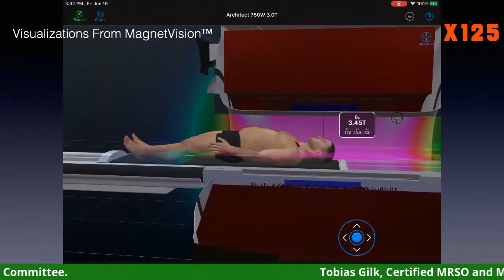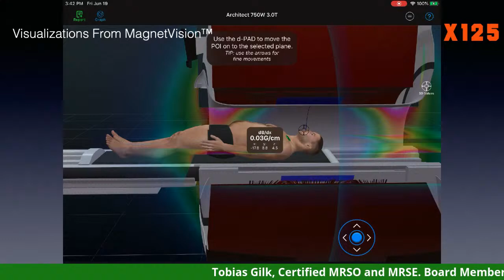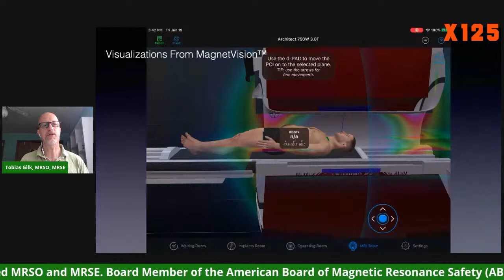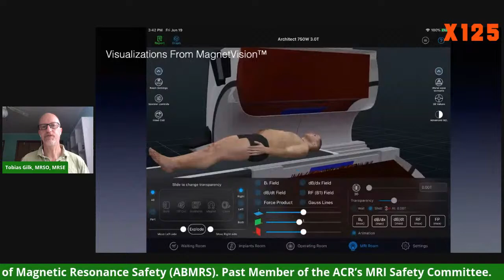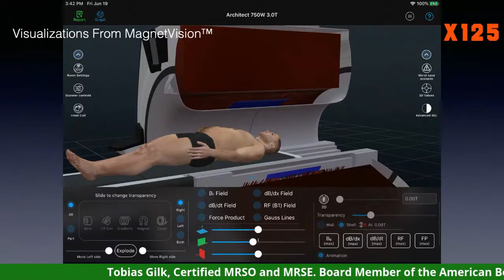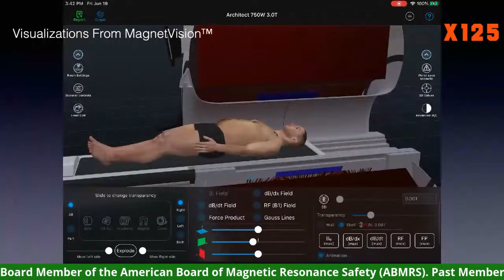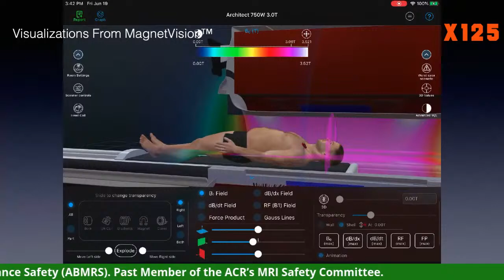And here we switch to spatial gradient. You'll see there's zero spatial gradient, or zero colorization, in the center. When we do point values, you can see that essentially it's functionally zero in the middle of the magnet. But you can see that there are regions near the mouth of the bore where the spatial gradient values are quite significant. It's incredibly important to have a good understanding. Let me see if I can just restart that animation. Here we go. Now you know what I'm describing. The fuchsia, the pink, is 3T values. The white is where it actually exceeds 3T.